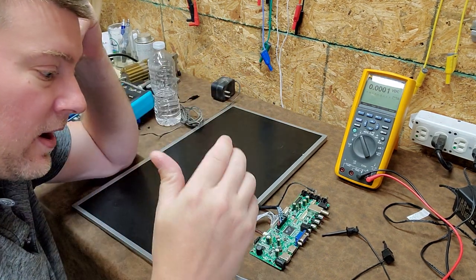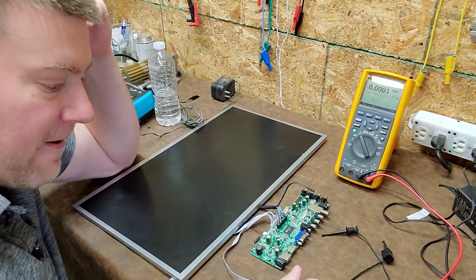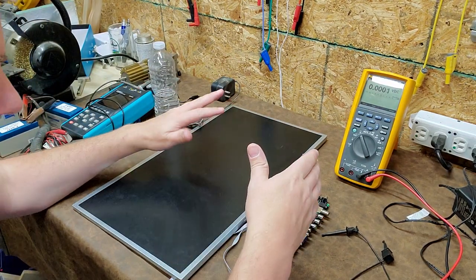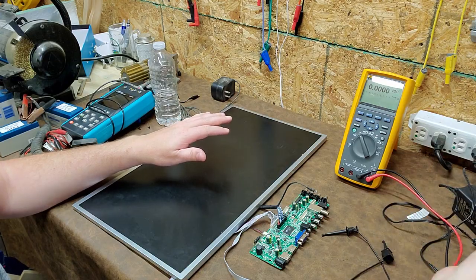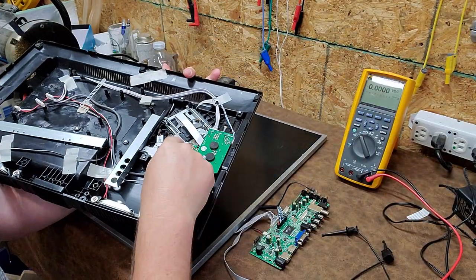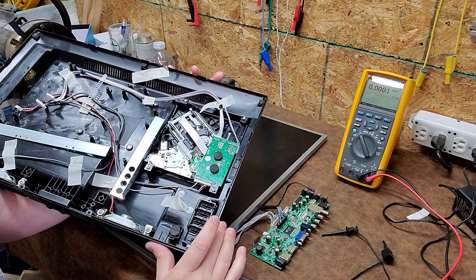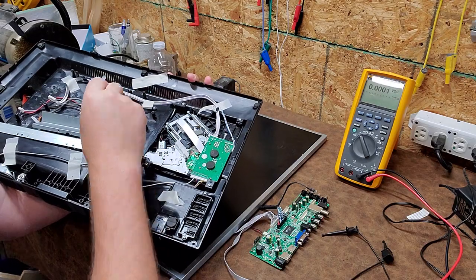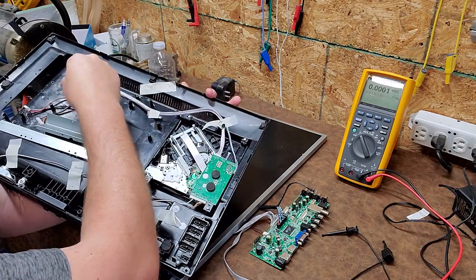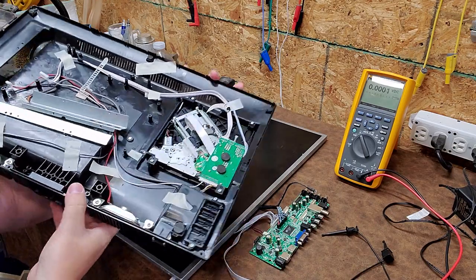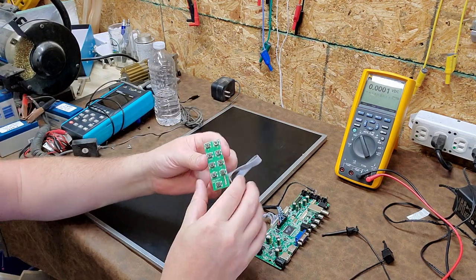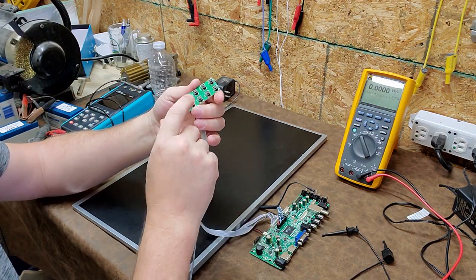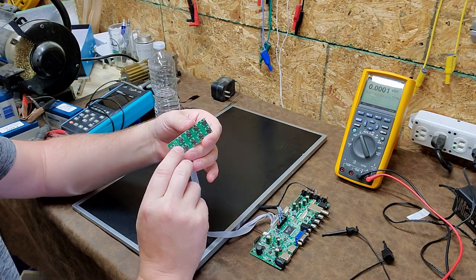I do believe that this is the kind of display that sits down near the patient. So the initial complaint was that the unit does not power on. I found a couple things that were a little suspect. You can see I've got the panel outside of its chassis. I've got the chassis sitting right here, and this also has an integrated DVD player, which none of that is necessary for testing the symptom that it's not powering on. So you can see I unplugged all the accessories from the main power board.